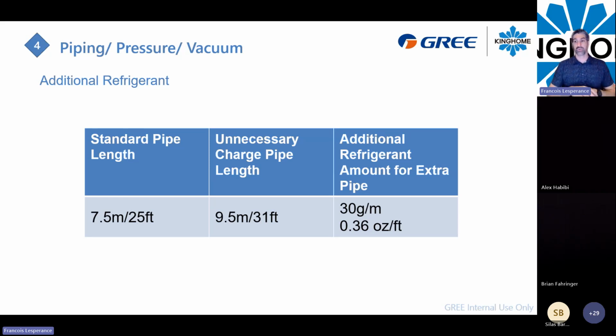So 0.36 ounce per feet extra. So that's how you will need to calculate the liquid line only. So only like how long is your liquid line, and everything's over your 31 feet, well, you will add 0.36 ounces per feet.